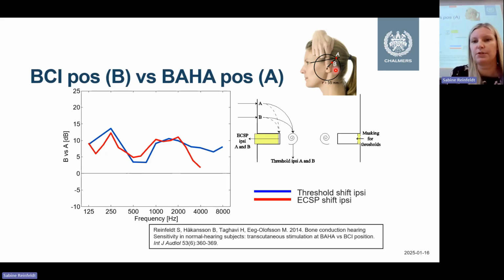So I don't know if this picture is too small now, but here you can see position A as where the BAHA is normally placed, and position B where we have the BCI. So A is a line from the eye on top of the ear, and then it should also be 55 millimeters from the ear canal. So it's here where those measures meet. And the BCI is placed a bit closer, as close as possible when we pull back the pinna like this. So this is made on normal hearing subjects.